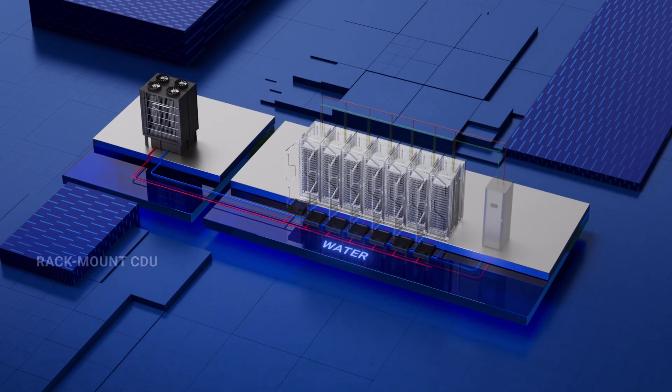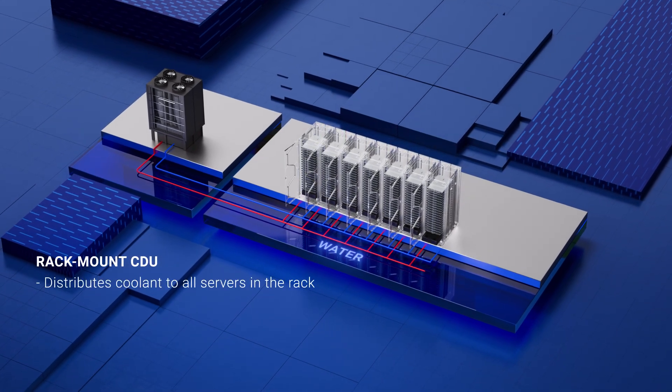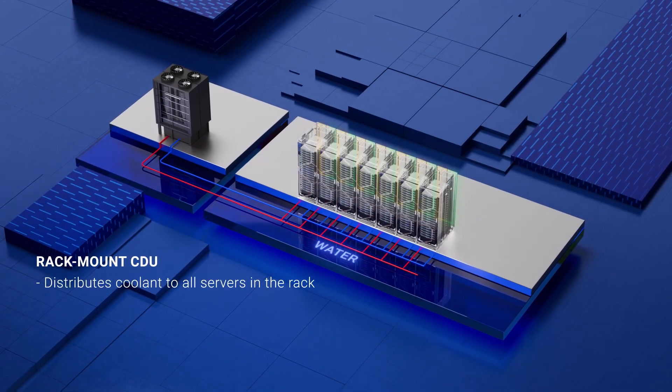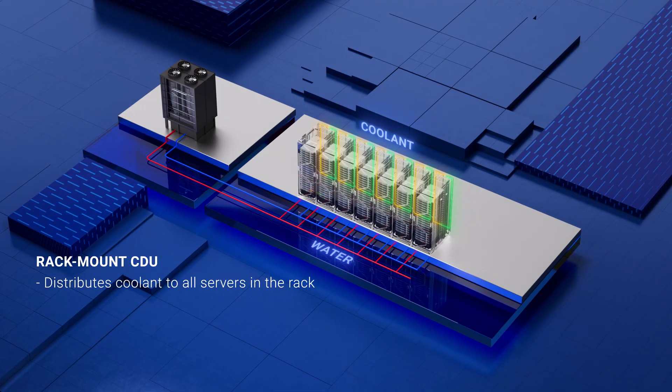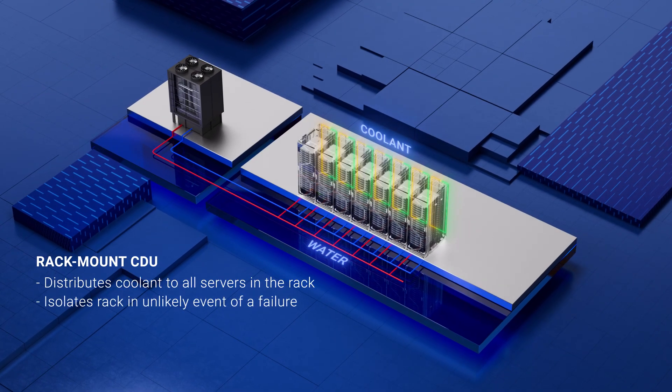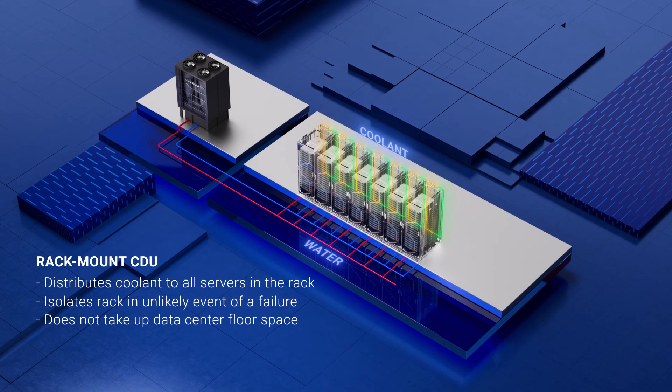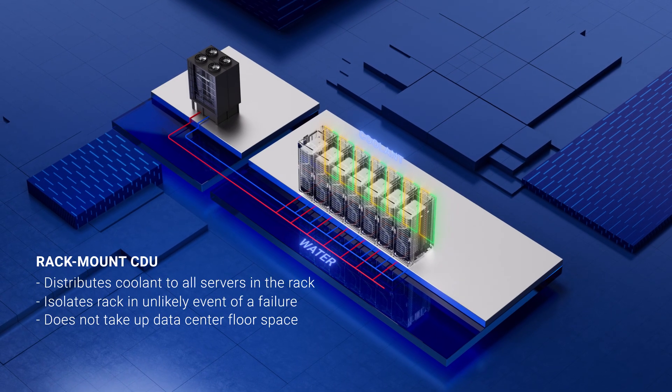A rack mount CDU distributes coolant to all servers in that rack. While they take up space in the rack, rack mount CDUs reduce the amount of compute infrastructure impacted in the unlikely event of a failure. And these are only the building blocks of a liquid cooling environment.